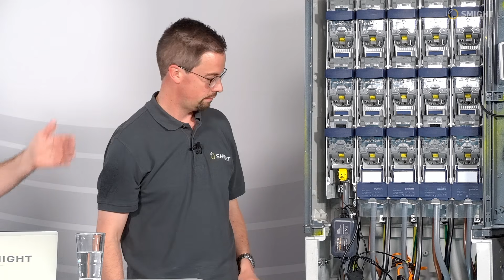And you said it's our Rogowski coils—so how is the connection to a power supply in that case? Yeah, so that's the one downside of Rogowski coils, is that they can't do the energy harvesting. So we've already put in here a power supply, and we work with a company who has these special connections, which means that you don't need to put a socket in. You can connect into the infrastructure very simply within the installation situation.